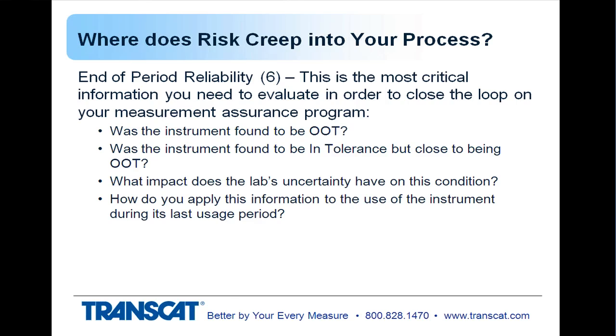And then this gets into the lab's uncertainty, measurement uncertainty, and how this impacts that close to being out of tolerance region. How do you use this information to determine how it affected your product or your decisions about the product or tests that you ran during the last calibration period?